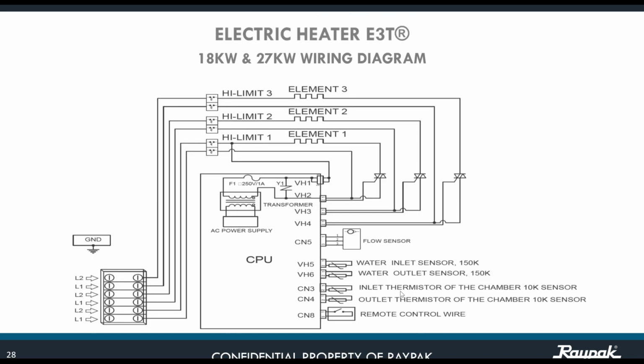Okay. For the 27 kilowatts, you're also going to have the same diagram, but it's going to be amplified in points of connection. Now you have L2, L1, L2, L1, L2, L1, and perhaps you're going to have 3 wires for ground, three high limits, 3 elements, and your flow sensor and your water inlet and outlet sensors. But there is also going to be an extra sensor right here, which is the thermistor of the chamber, and the outlet thermistor of the chamber. Those thermistors are going to be 10K sensors. So just keep in mind that the water inlet and outlet sensors are 150K, and the inlet and outlet thermistors are 10K, totally different. And once again, the remote control wire.